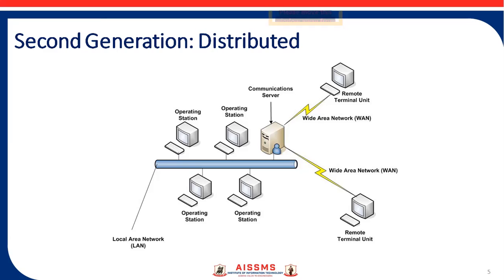Some of the LAN protocols used were of a proprietary nature, where the vendor created its own network protocol rather than adopting an existing off-the-shelf one. This allowed a vendor to optimize its LAN protocol for real-time traffic, but it limited the connection of networks from other vendors to the SCADA LAN. Distribution of system functionality across network-connected systems served not only to increase processing power, but also to improve redundancy and reliability of the system as a whole.